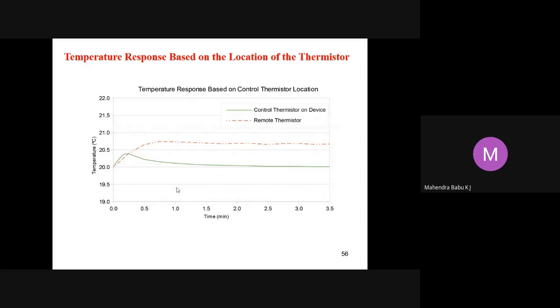So once the placement of the sensor has been chosen, the rest of the system needs to be configured. This includes determining the base thermistor resistance, the bias current for the sensor, and also the set point temperature of the load on the temperature controller.